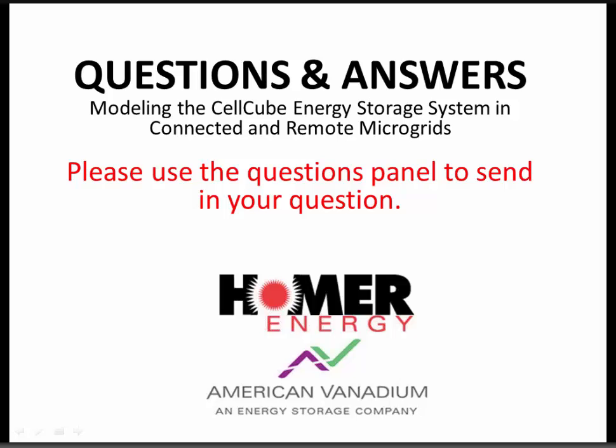In other words, we can have, as was shown in the presentation, a 200 kilowatt battery with 2 hours or 4 hours or 8 hours. So, by definition, a dollar per watt number really doesn't make any sense, because it's obviously going to be different for those different durations. So you have a very non-linear set of metrics in the cost equations.